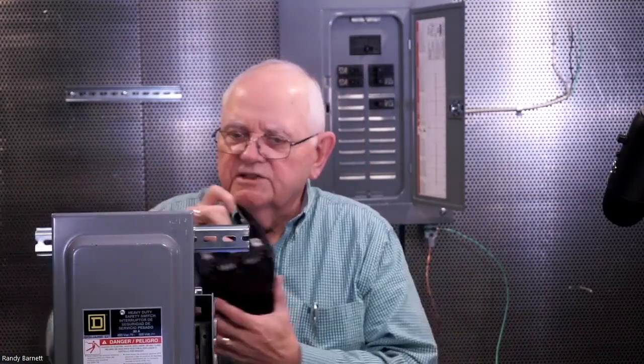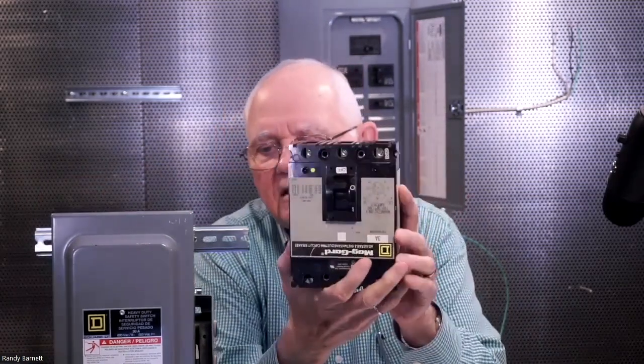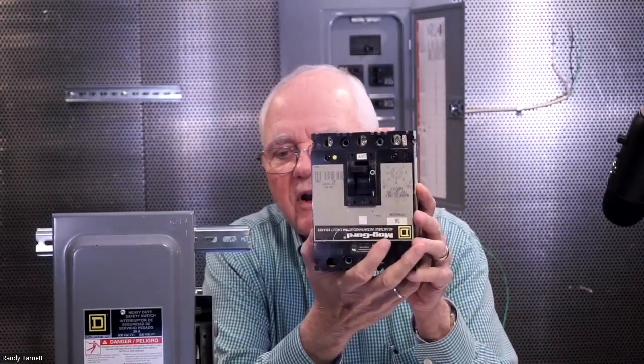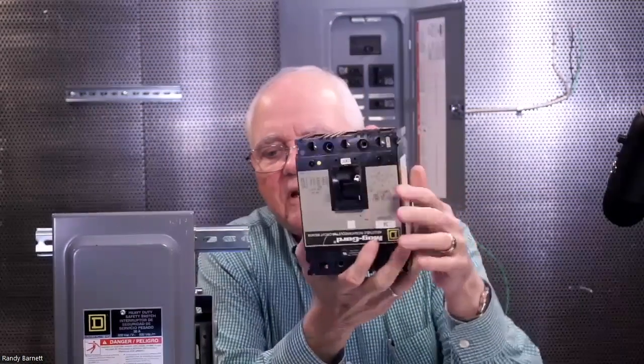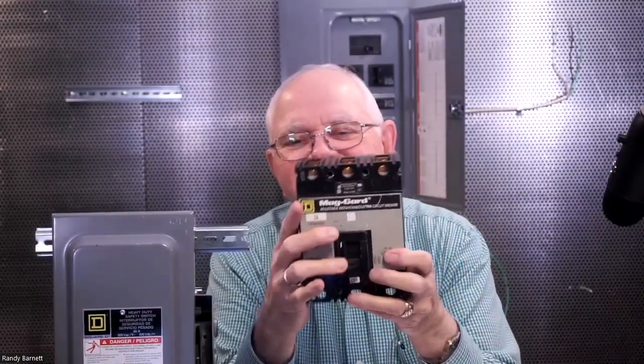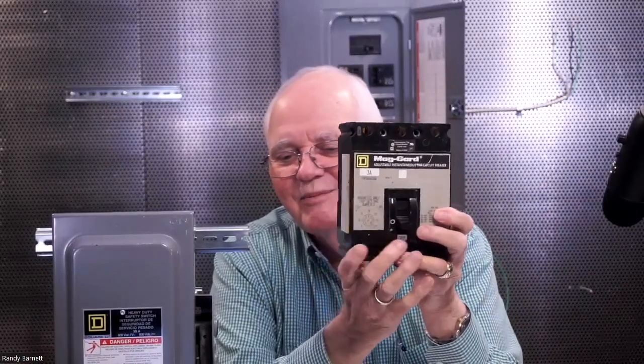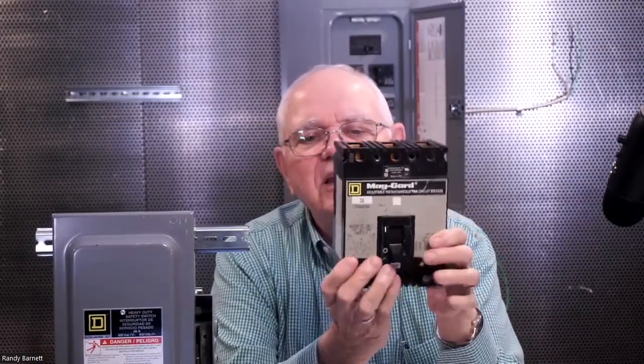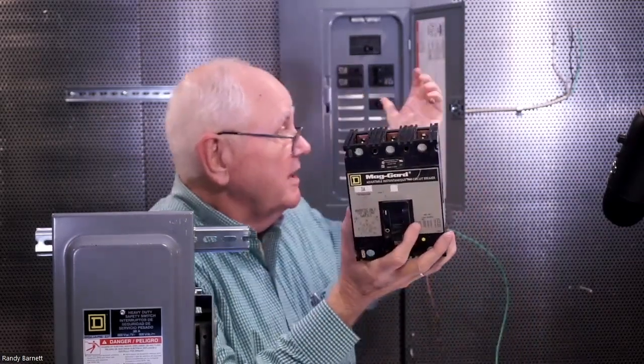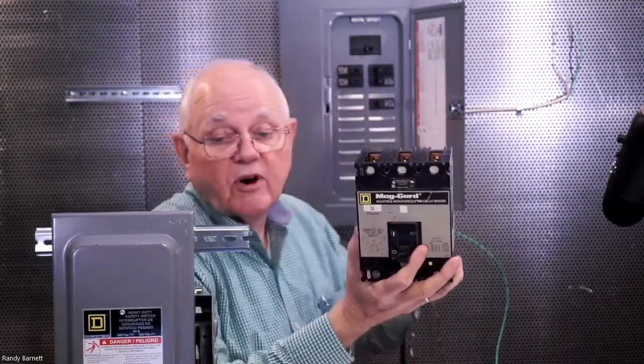One more thing that I can use for disconnecting means, and you'll see this quite a bit, is an instantaneous trip circuit breaker. The handle's right here in the middle. Turn it right side up for you. Got some information over here. Let's see what it says. It says it's magnetic only, trip setting in amperes. So it's magnetic. The breakers behind me up here are thermomagnetic breakers, right?